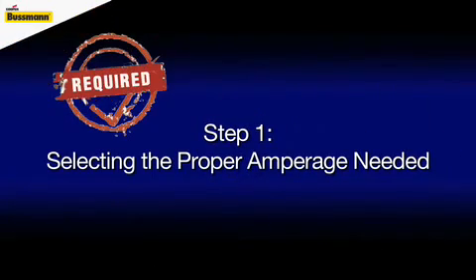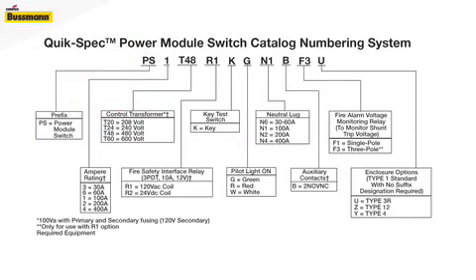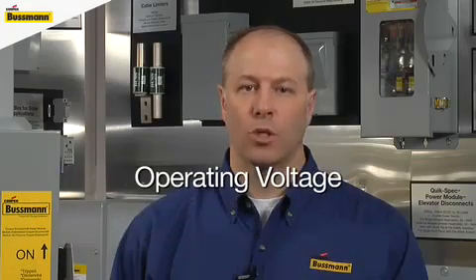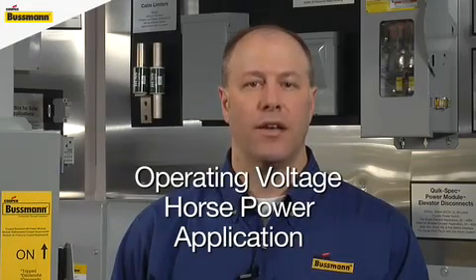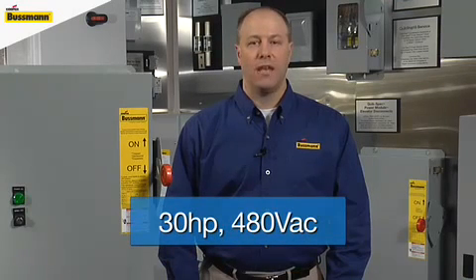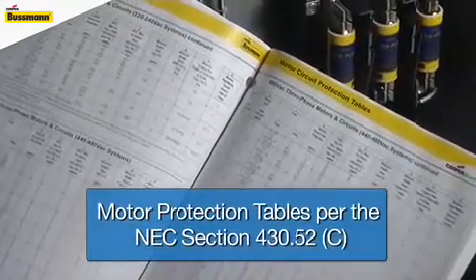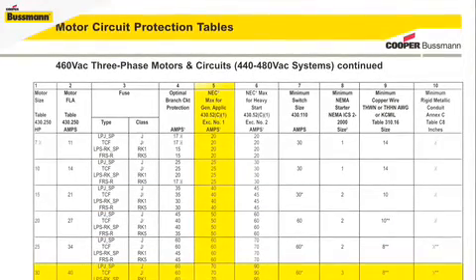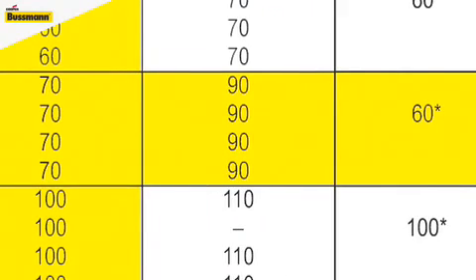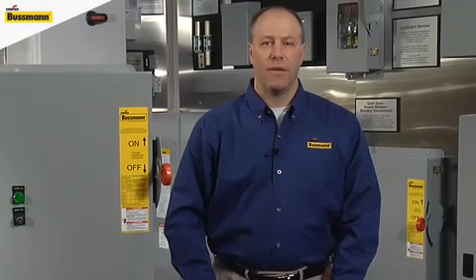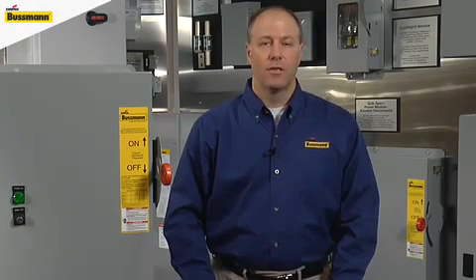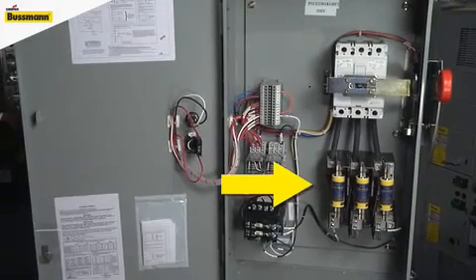The first step in a nine-step process for building a power module switch part number is to determine the switch amperage needed. For this, you will need the operating voltage, horsepower rating, and application the elevator is designed to operate. For our example, we will use a motor with a 30 horsepower rating at 480 volts AC. As we look at the NEC section for 30 horsepower, we can see the proper sizing for a general duty elevator motor would be 70 amps. If the elevator is a freight elevator, it might be better to size it accordingly with 90 amp fuses. Cooper Bussmann offers Class J time delay fuses to fit this application. The 70 amp through 100 amp fuses all fit into the 100 amp power module switch.